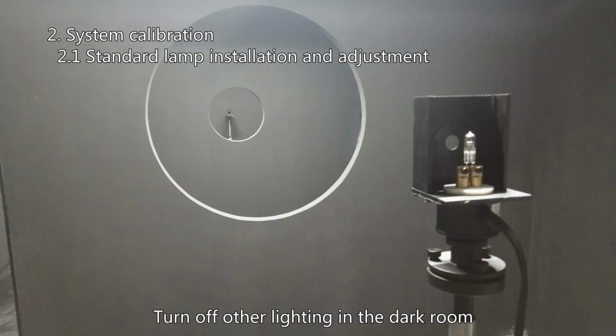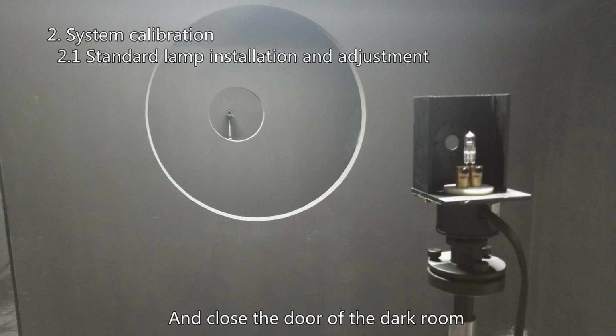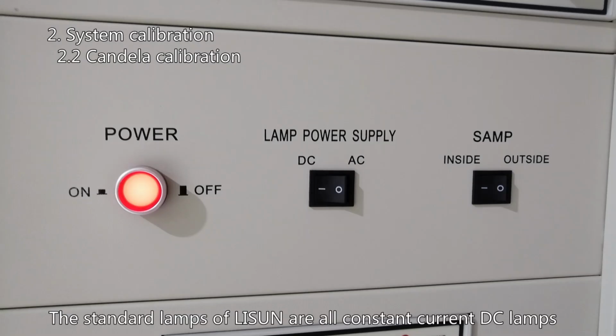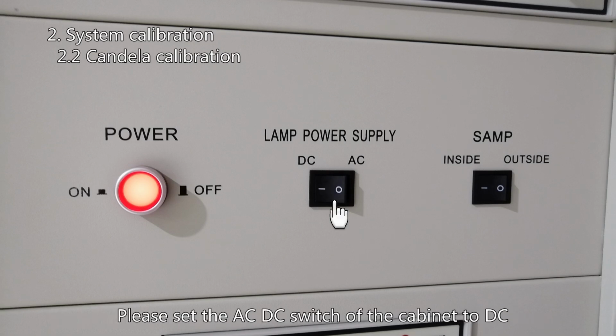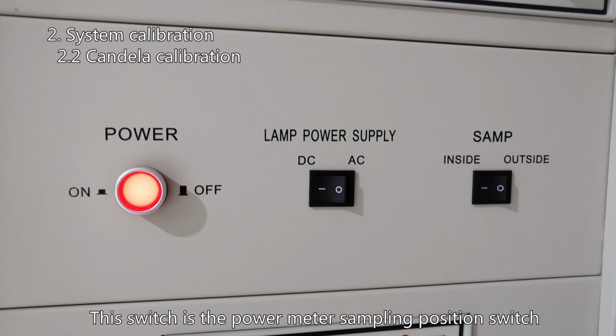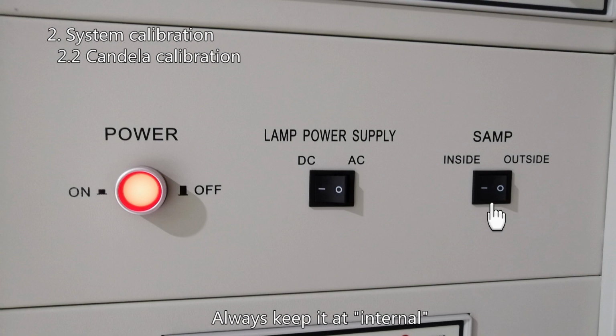Turn off other lighting in the dark room, and close the door of the dark room. The standard lamps of LISUN are all constant current DC lamps. Please set the AC-DC switch of the cabinet to DC. This switch is the power meter sampling position switch. Always keep it at internal.